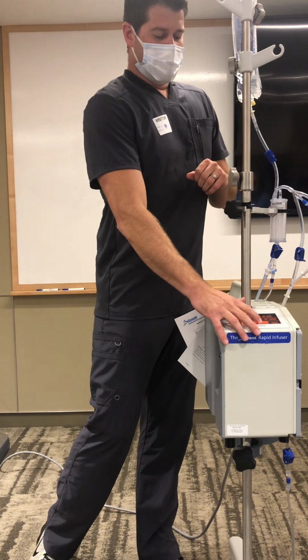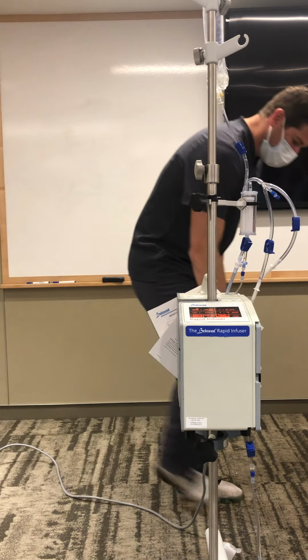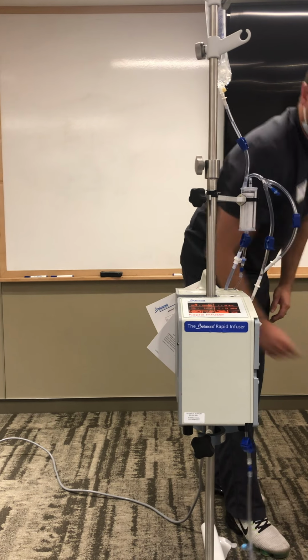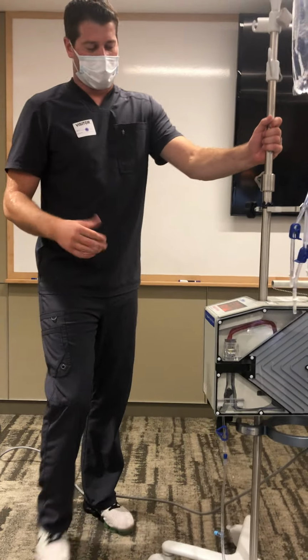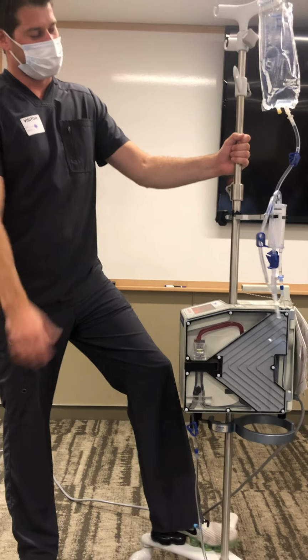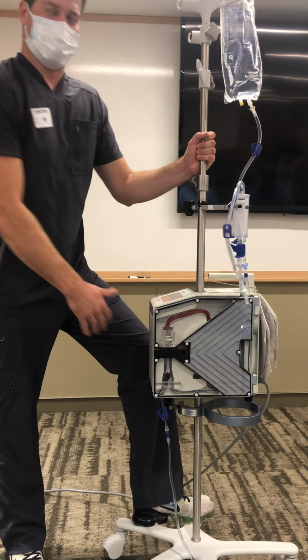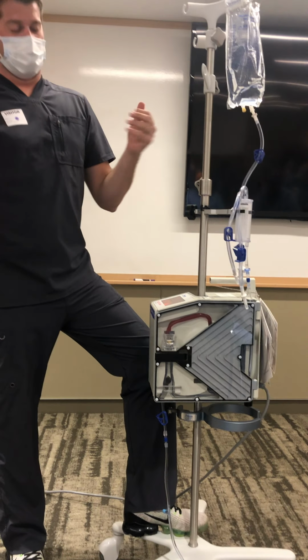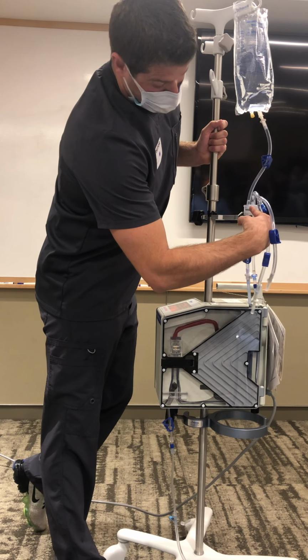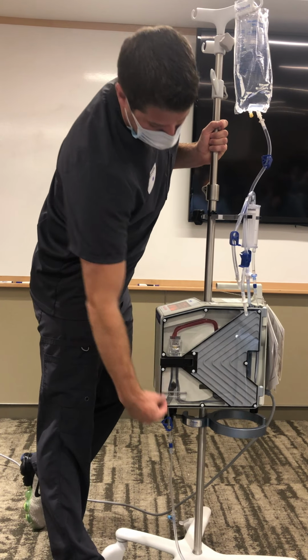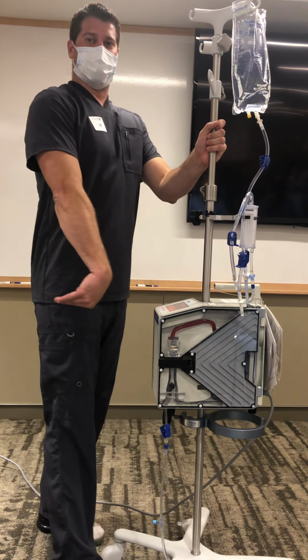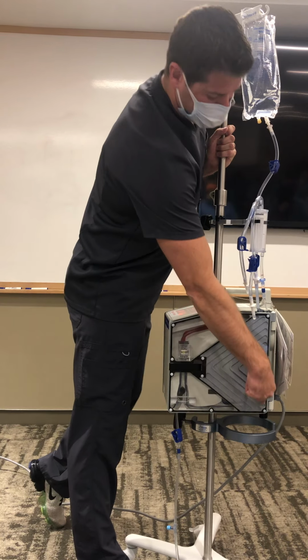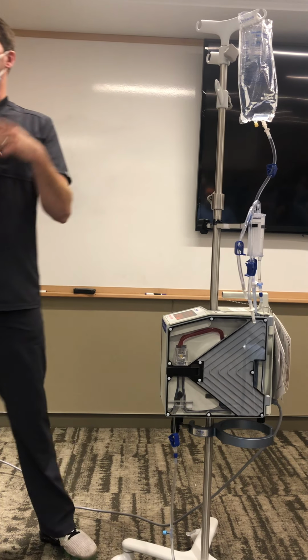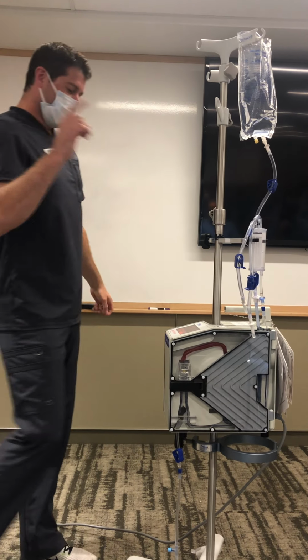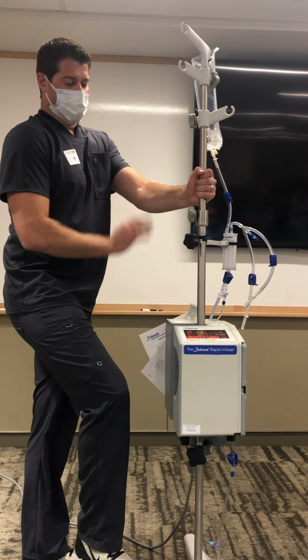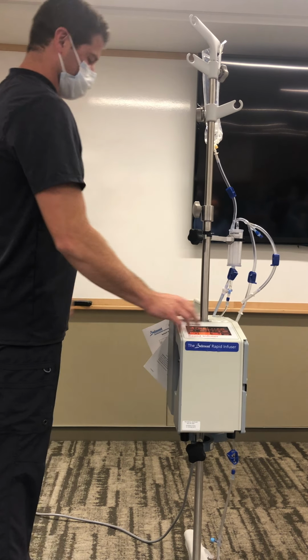Recirculate. There are two main purposes for recirculate. Say you've gone into standby mode for a while—1 minute or 10 minutes, doesn't matter—and you're worried about your blood getting stagnant and clotting in the line because it's not moving. By hitting this recirculate button, it grabs the fluid and runs it through the circuit, but instead of sending it out to the patient, you can see our patient safety wand has slid over, so you're not infusing—it's redirecting the fluid to the recirculation line back up. It's like a little mini racetrack, keeping it turning and mixed up so you don't have to worry about your blood clotting. The other thing it's doing at the same time is warming, which leads me to scenario two.